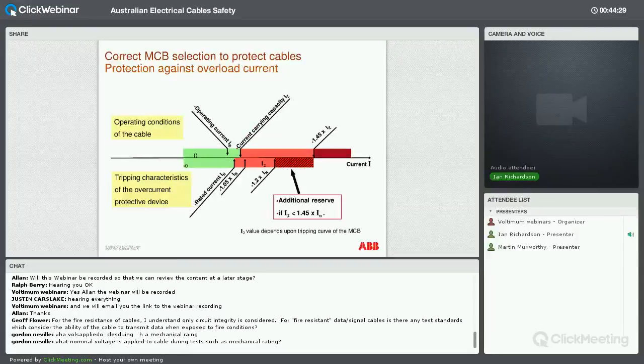So moving to that next slide, there's another way of looking at this. We've got the operating conditions of the cable on the top line. So there is an operating current, which is a normal operating current or load that we're trying to protect. Above that will be the current carrying capacity of the cable, depending on which cable has been chosen. In the design of the cable, manufacturers put this 1.45 value in there, which is our additional reserve value, or an overload that the cable is actually designed to take. So it's 1.45 times the current carrying capacity of the cable.